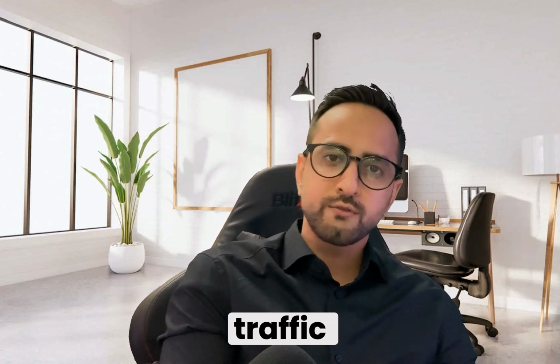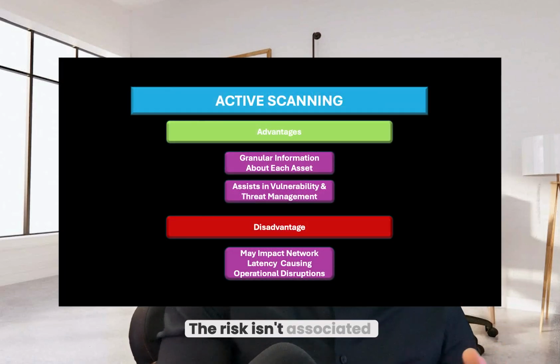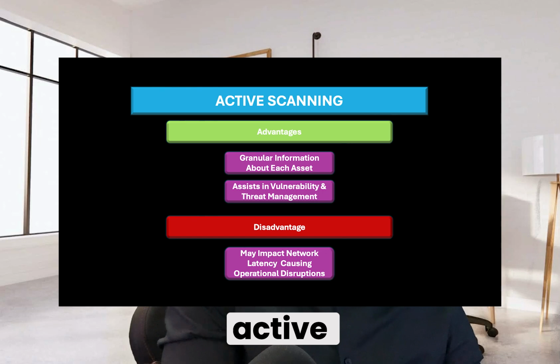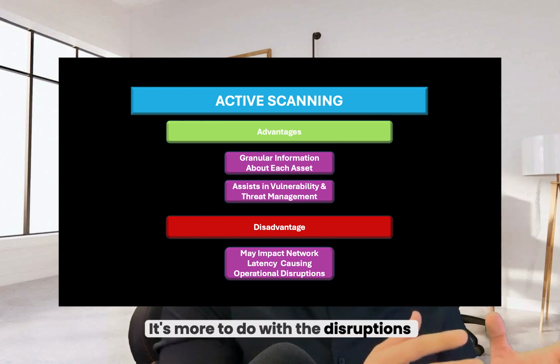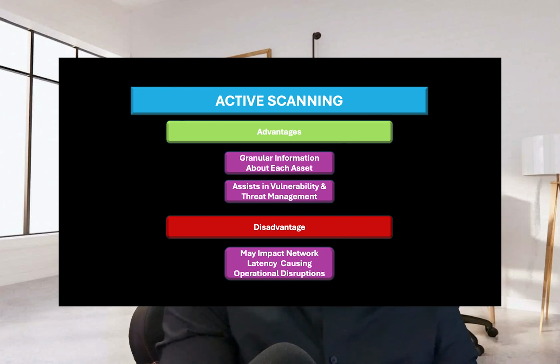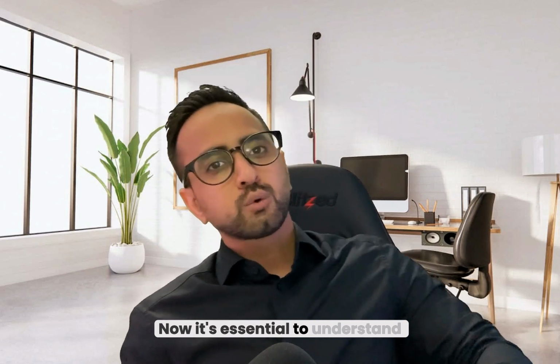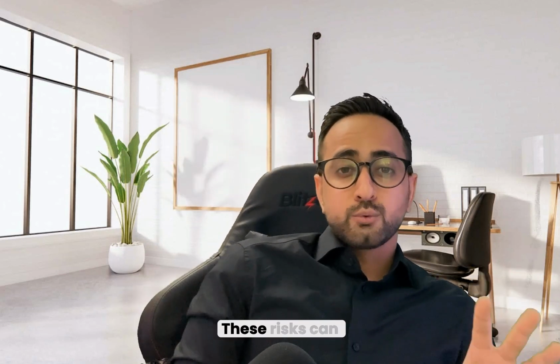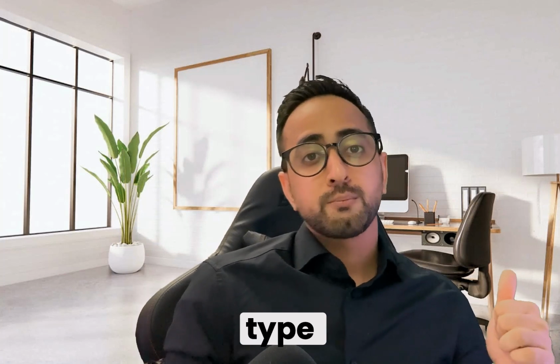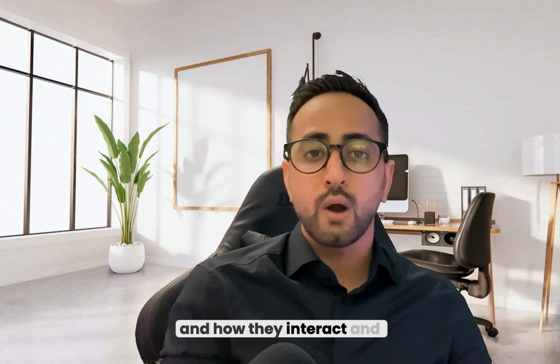Many OT devices like PLCs and SCADA systems are sensitive to OT network traffic in general. The risk isn't associated with the systems shutting down through active scanning. It's more to do with the disruptions and causing latency issues for those systems. Now, it's essential to understand the elements of impacting systems like PLCs. These risks can be due to the type of content sent by the scanning tool, the type of PLCs, and how they interact and respond to scanning packets.